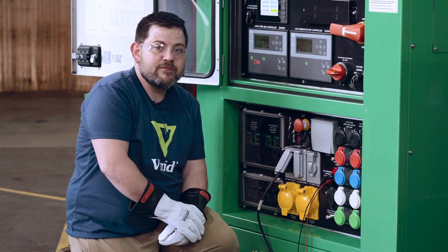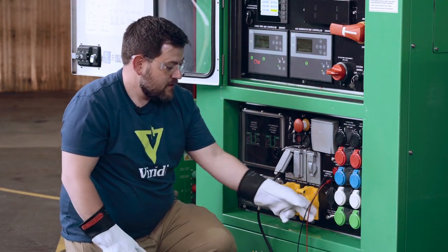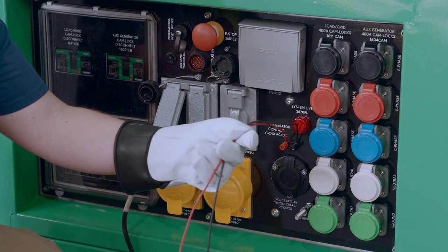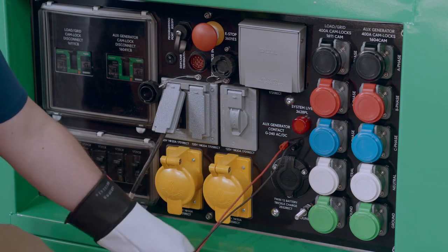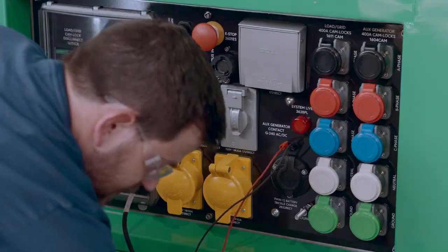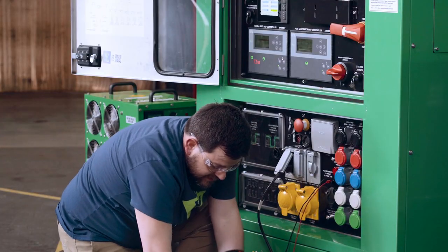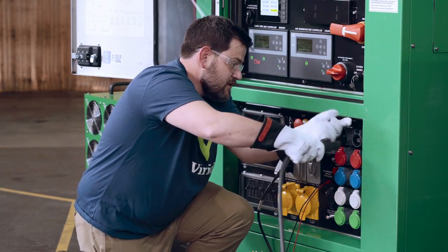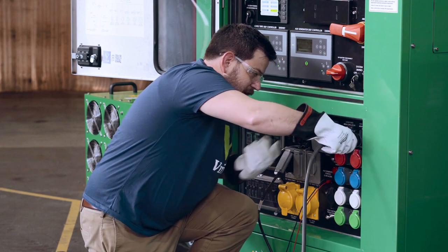Next, we're going to go through a generator hybrid setup. I'm going to do this connection at a 208 volt setup. Currently, we already have the 2-wire remote start wire connected to our generator and to our SBR unit. I will then connect our generator connection to our auxiliary generator connection point, the cam locks.